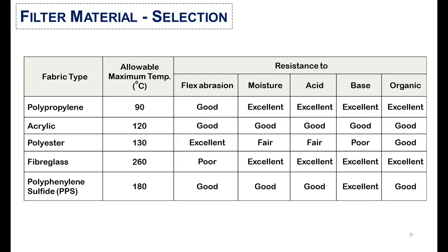Here is the selection criteria for filter material. The fabric type depends upon the allowable maximum temperature and the contamination of the dirty gas. If the service temperature is low — say up to 90°C — then polypropylene fiber type is selected, because it shows good resistance to moisture, acid, base, and organics.